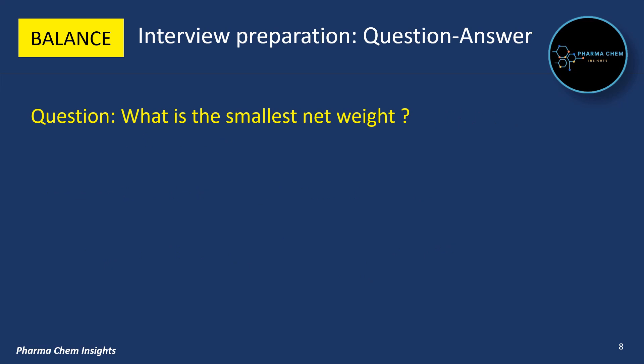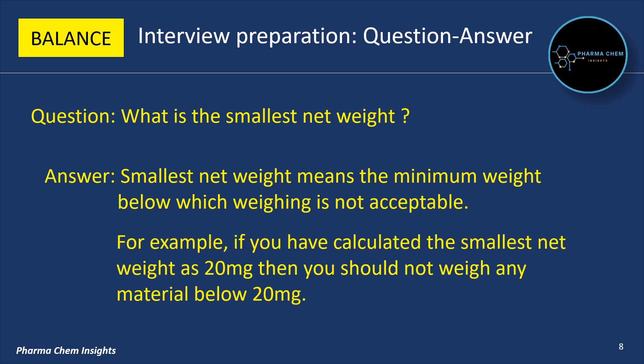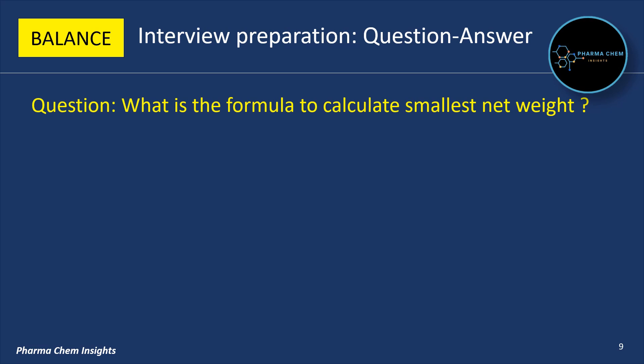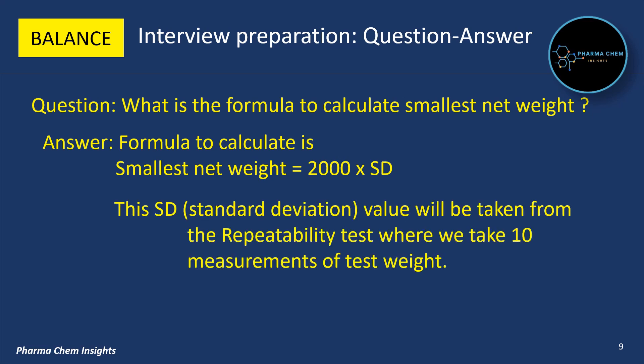Next question: what is the smallest net weight? Smallest net weight means the minimum weight below which weighing is not acceptable. For example, if the smallest net weight is calculated as 20 mg, then you should not weigh any material below 20 mg. The formula to calculate smallest net weight is: SNW = 2000 × SD, where the SD value is taken from the repeatability test in which 10 measurements of the test weight are taken.